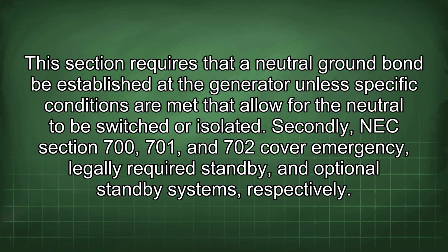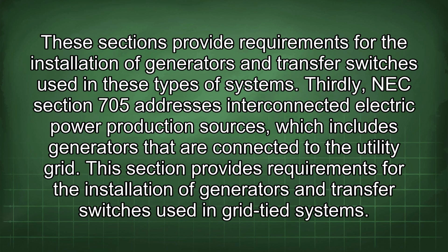Secondly, NEC Sections 700, 701, and 702 cover emergency, legally required standby, and optional standby systems, respectively. These sections provide requirements for the installation of generators and transfer switches used in these types of systems. Thirdly, NEC Section 705 addresses interconnected electric power production sources, which includes generators that are connected to the utility grid. This section provides requirements for the installation of generators and transfer switches used in grid-tied systems.